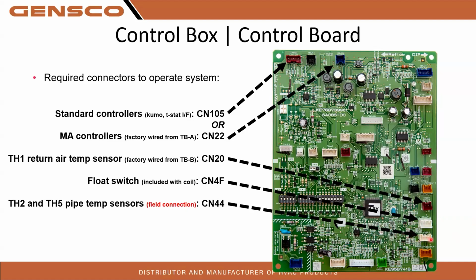CN44, this is for the coil thermistors. So those coil thermistors that are tied into your coil from the factory, that's where they're going to plug into right there. So this is that connector that has to be within 5 feet, or why the control box needs to be within 5 feet of the coil, because of those thermistors right there.